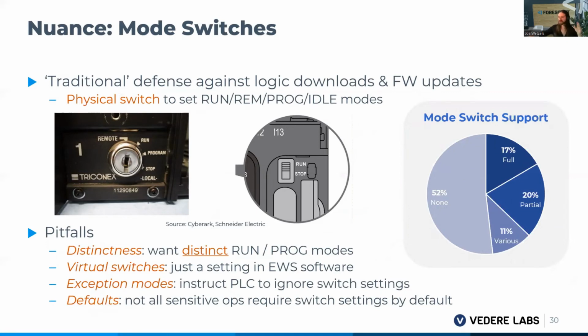Finally, some nuance regarding mode switches. These are a very traditional defense in OT against malicious configuration, logic downloads, firmware updates, and so on. They consist of a physical switch on the controller that regulates the PLC's mode of operation, enforcing that certain engineering operations require someone with physical presence rather than an attacker with only logical network access.